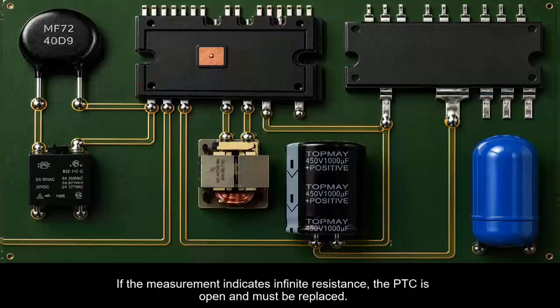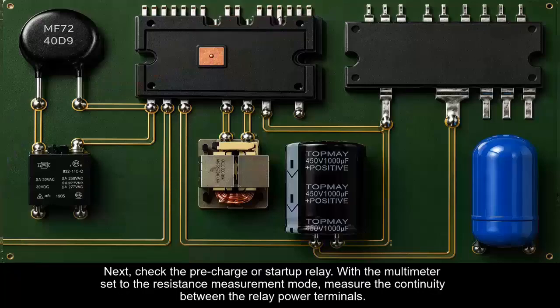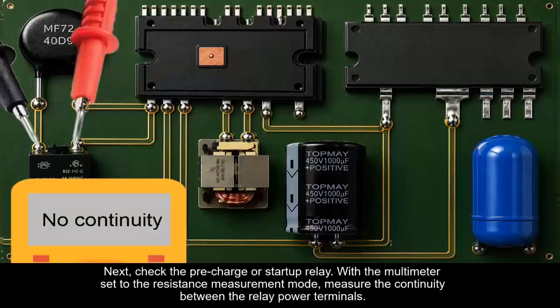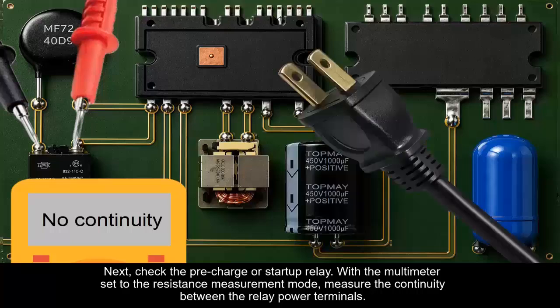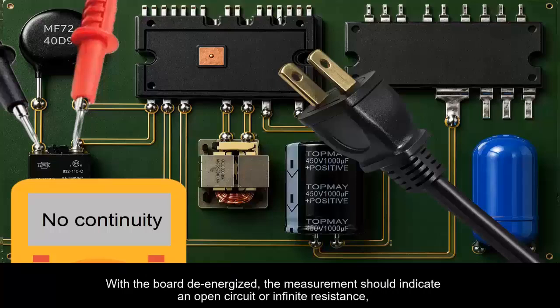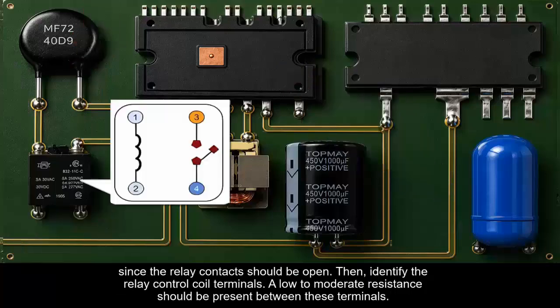Next, check the pre-charge or startup relay. With the multimeter set to the resistance measurement mode, measure the continuity between the relay power terminals. With the board de-energized, the measurement should indicate an open circuit or infinite resistance, since the relay contacts should be open. Then, identify the relay control coil terminals.